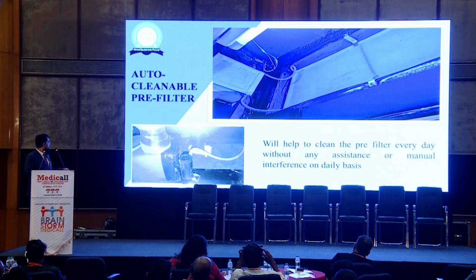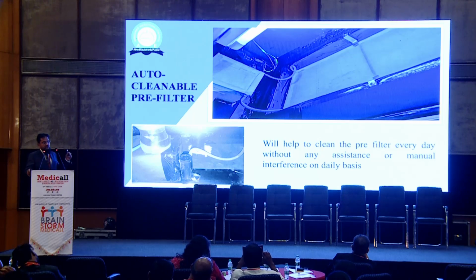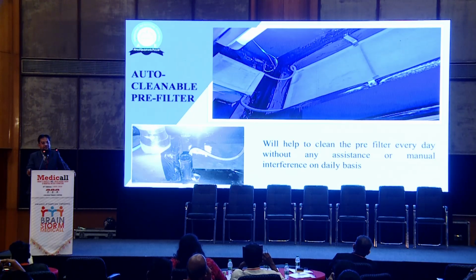You can see what we have done. We have done one small reservoir of half a liter where the motor is also there. When you switch off the system, the motor will start, and within a minute both these filters will get pressurized clean. So these are washable, cleanable filters we have given. Both these filters will get clean, so routine maintenance is totally taken care of.